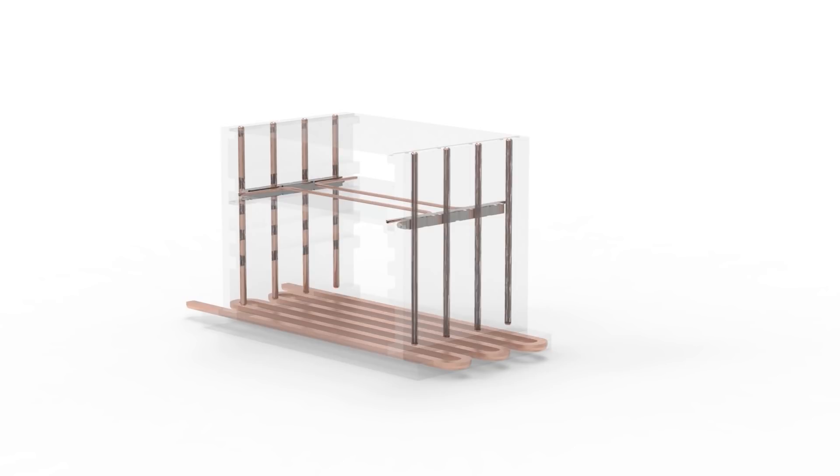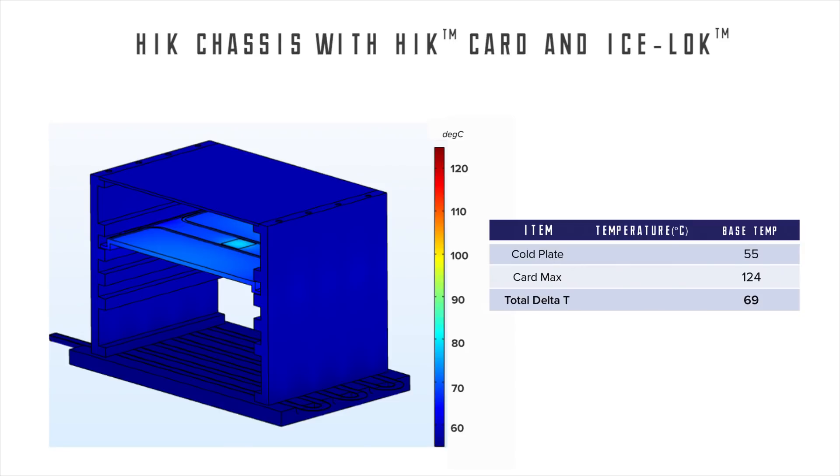The final area affecting overall delta T is the conduction through the card guide or chassis. Each sidewall must conduct heat from the card interface to the liquid-cooled base. Again, the baseline is aluminum with a thermal conductivity of 167 watts per meter Kelvin. To reduce the gradient, we convert the chassis to a high-K sidewall by embedding heat pipes. This final change drops the overall delta T by an additional 13 degrees C.